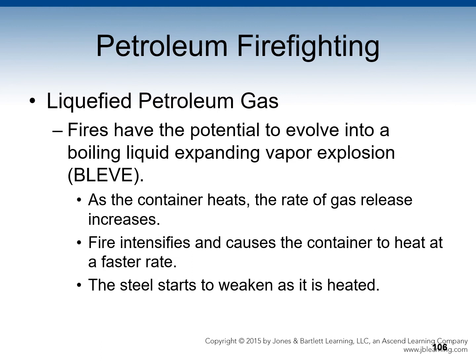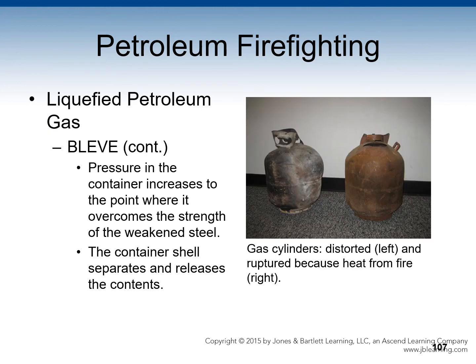One concern with these types of fires is the potential for the fire to evolve into a boiling liquid expanding vapor explosion, or BLEVE. When the fire is burning from the relief valve on top of the tank, the container is heated from radiated heat. As the container is heated, the rate of gas release increases, which intensifies the fire, which in turn heats the container at a faster rate. Steel starts to weaken as it is heated. When the pressure in the container increases to the point where it overcomes the strength of the weakened steel, the container shell will separate, releasing the contents.